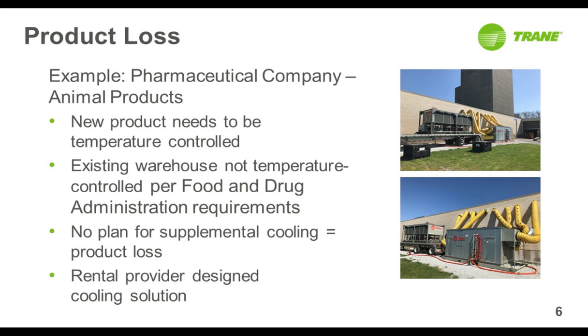Installing permanent cooling would result in further loss of product, so they leaned on a rental provider and a rental solution. As you can see in the pictures, they were able to bring in a temporary air-cooled chiller and a temporary rental air handler, and they were able to provide temporary cooling to the plant.